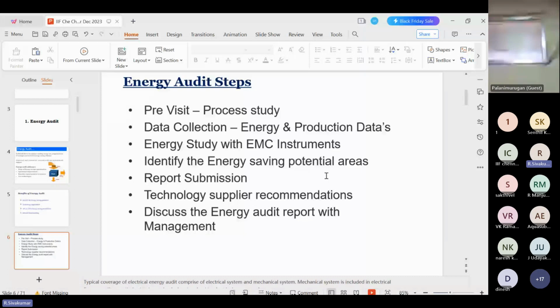Then we will plan for the detailed energy audit. So when we are doing the detailed energy audit, we are carrying some energy measurement instruments, that is EMC instruments. So we will spend some 3 to 4 days, depending on the plant size. The number of days will vary. For a small unit, 1 or 2 days is sufficient. A bigger foundry or bigger unit may need maybe 1 week.